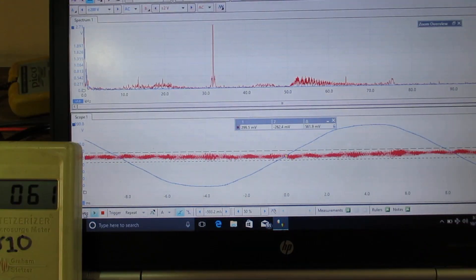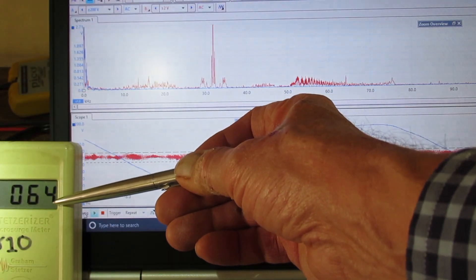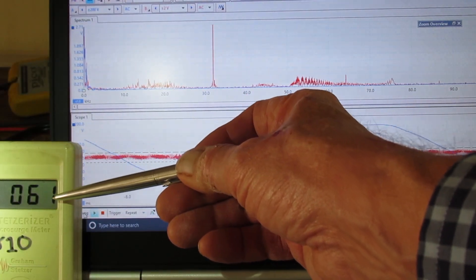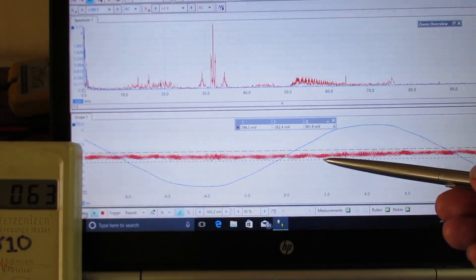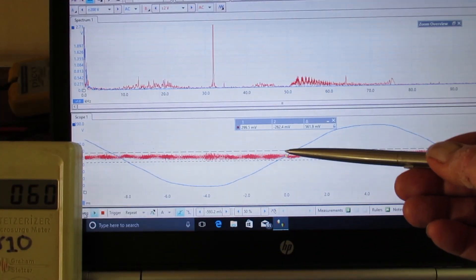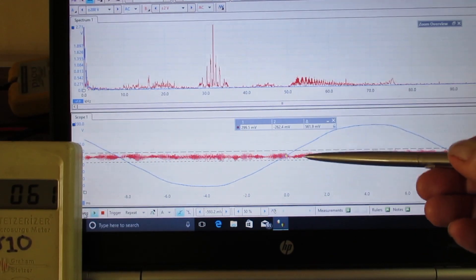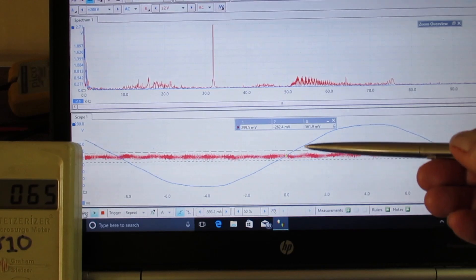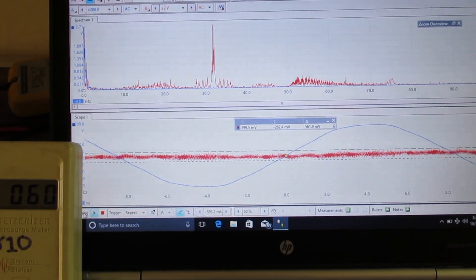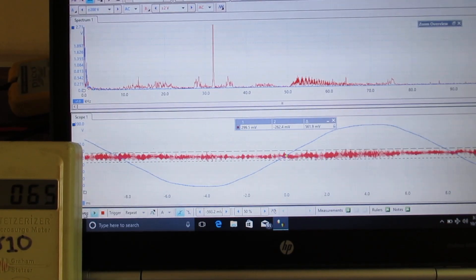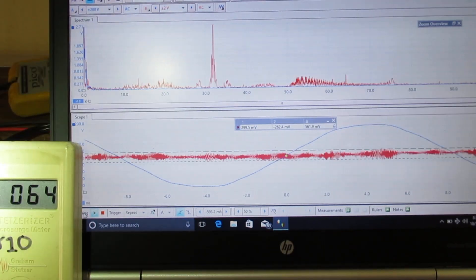Keep in mind, with the inverter off, we have 60 GS units. That's not good, but that's what's coming in from the utility. The voltage transients — the absolute outside — is somewhere around 560 millivolts peak-to-peak. That's enough to cause pain and suffering for a lot of my clients, but it gets much worse when the solar inverter is on.